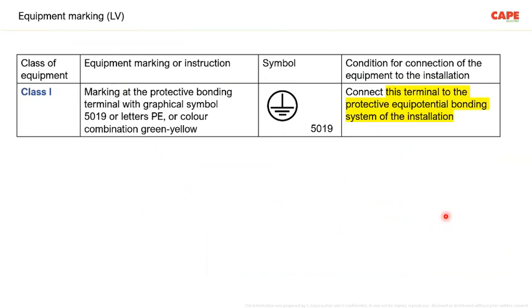And what I wanted to explain to you is that electrical equipment is classified into class 1. Class 1 means an equipment, for example, a motor. In case of an insulation failure inside the motor, its body becomes exposed to a voltage, and if somebody touches this body, he will get a shock. The manufacturer's responsibility is to make an earth terminal on that equipment, and put either the number 5019 or the letters PE or the color combination green and yellow. This is the symbol of protective earthing.